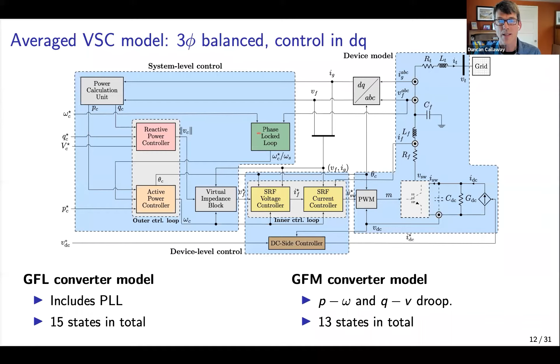Okay, so finally, before I do my final dive into getting into the results, the network model, I want to talk about this very briefly. I'll show you some initial results with a very simple network, just 2 buses. We've got a power electronic converter on one bus, a synchronous generator on the other bus, and loads on both sides. I'm going to explore first a situation where the line between those buses is just what we call an algebraic representation, meaning that there's no dynamics in voltage or current on that line. We just take whatever is happening on one side and assume the same thing is happening on the other, mediated by some static impedance. But then we'll look at a case where we say, what if there are voltage and current dynamics on that line, and how does that change the conclusions that we make about stability?